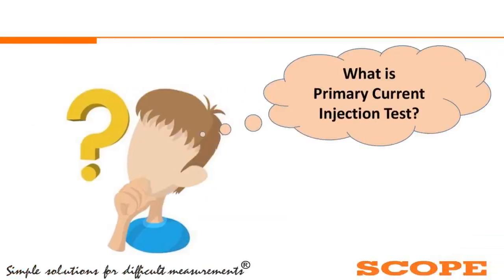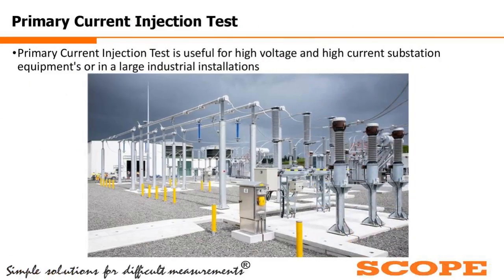The first question in our mind: what is the primary current injection test, and what are its applications? Basically, the primary current injection test is very useful for high voltage and high current substations — for testing current transformers, circuit breakers, or checking the healthiness of relays and circuit breakers in larger industrial installations.